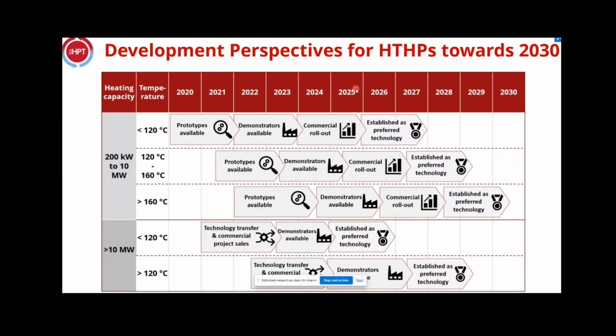They are expected to be commercially available during 25, and then for even higher temperatures, there's a bit more delay. There are also systems for even higher capacities, above 10 megawatts. This is typically integrally geared turbo compressors, for example, known from process gas compression. They're quite advanced, they're available, they are commercially offered, and we are waiting for the first projects in industries reaching the temperatures indicated. But again, they are typically used in way more challenging applications. So here we believe that they certainly can do the job and be applied for heat pump technologies also.